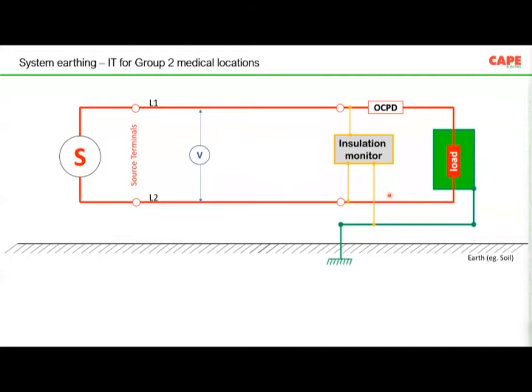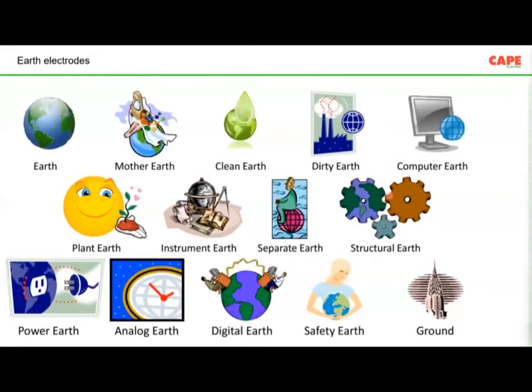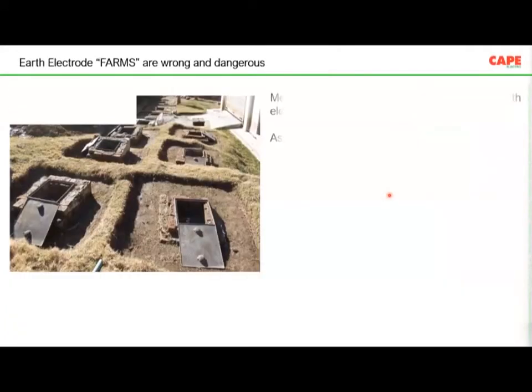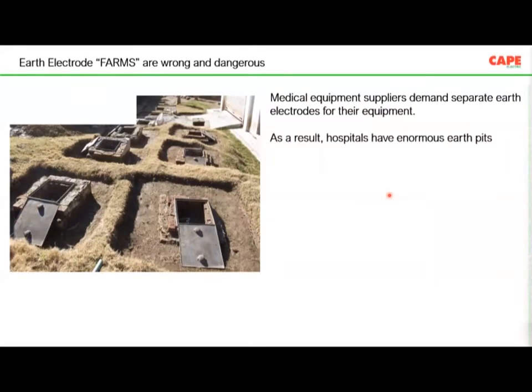No, it is not like that. You have to have so many safety measures. One of the safety measures is the medical IT system. But whenever it comes to the earthing system, actually the first part which we are missing is earthing. And everywhere, so many earth electrodes. There are hospitals with more than 150 to 200 earth electrodes all around. So we make a kind of an earth farm.